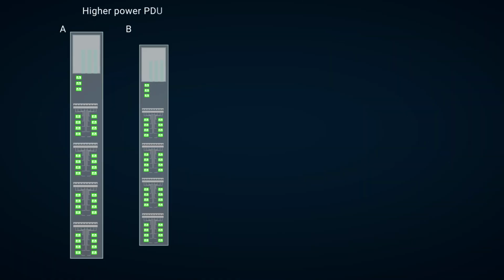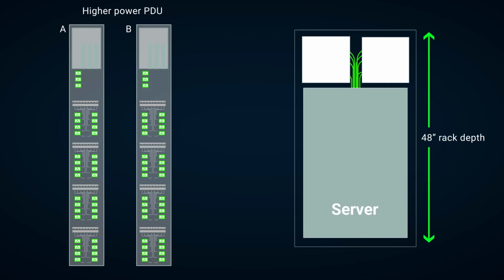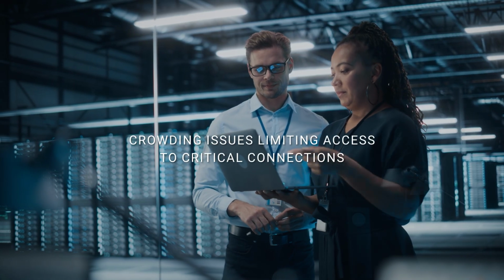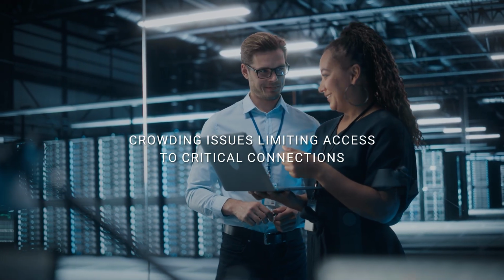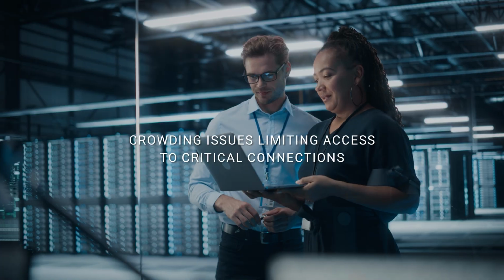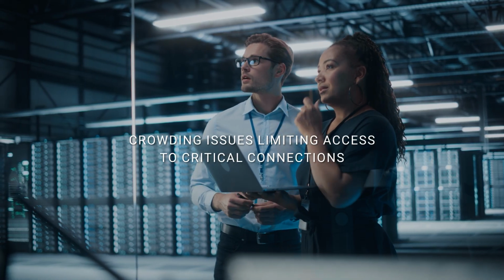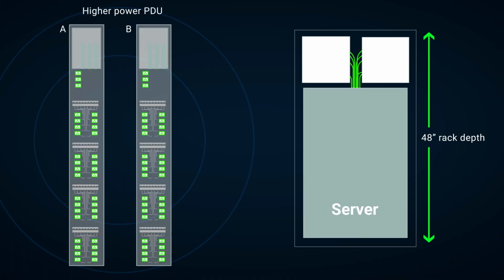The challenge doesn't end in the power distribution space. As you can see, when scaling to 100 kilowatts inside the server cabinet, data center operators will be met with the same crowding issues, which limits access to critical connections, restricts airflow, and makes changes exceptionally difficult. The size of the server cabinet PDUs to support 100 kilowatts in a single cabinet becomes impractical.